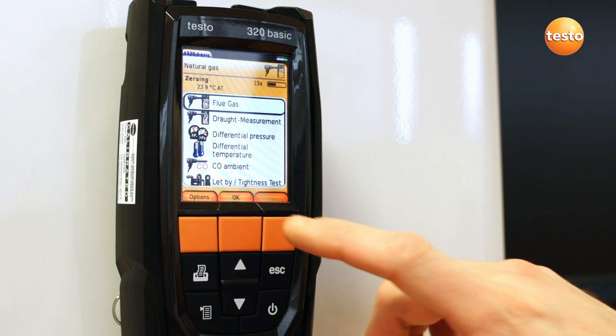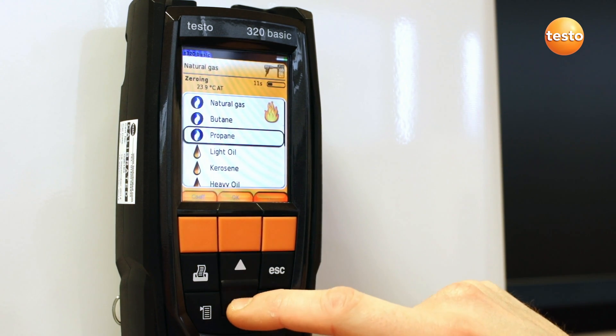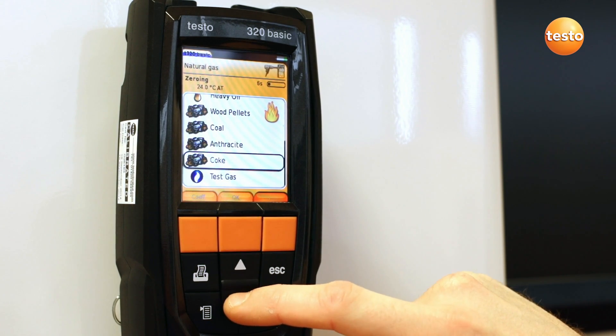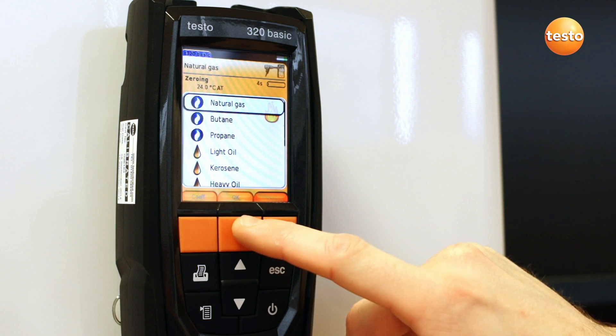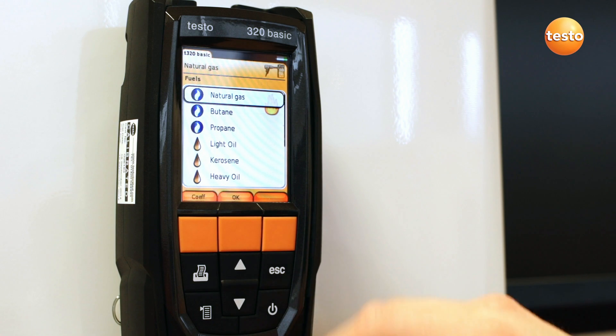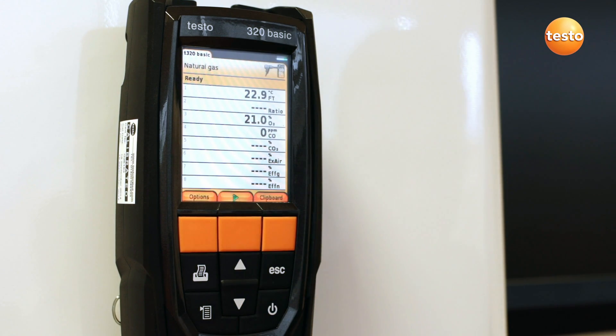The 320 basic sensor zeroing takes just 30 seconds, and during this time you can select the flue gas test from the menu and select the required fuel type from the list. The analyzer should show 21% oxygen if it has been zeroed in fresh air.